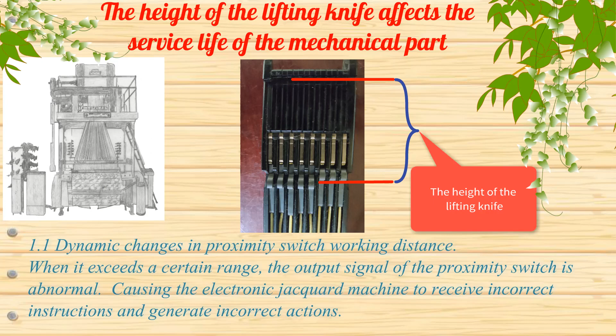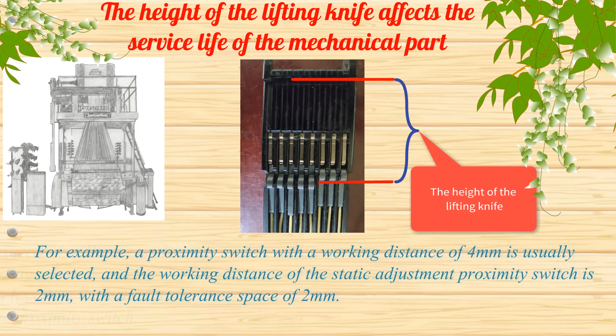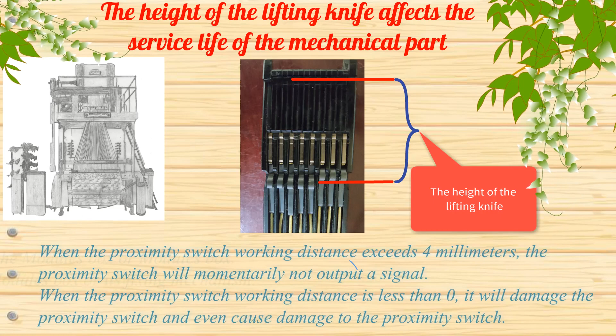For example, a proximity switch with a working distance of 4 mm is usually selected, and the working distance of the static adjustment proximity switch is 2 mm, with a fault tolerance space of 2 mm. When the proximity switch working distance exceeds 4 mm, the proximity switch will momentarily not output a signal. When the proximity switch working distance is less than 0, it will damage the proximity switch.